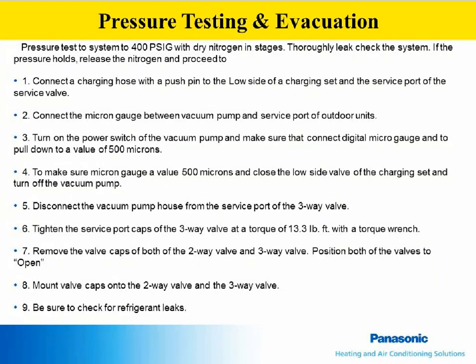Next, release the nitrogen pressure and connect your vacuum gauge and pump. Pull the system down to 500 microns. If 500 microns cannot be attained, there is either a leak or contamination in the lines. If no leaks are found, you can usually pressurize the system with nitrogen and vacuum it several times to clean it out. When 500 microns is reached, close off your gauges and turn the pump off. The system should be held in this vacuum for a minimum of 30 minutes to an hour. Continue with the rest of the installation while vacuuming and pressure testing.